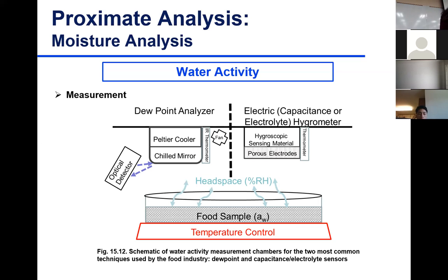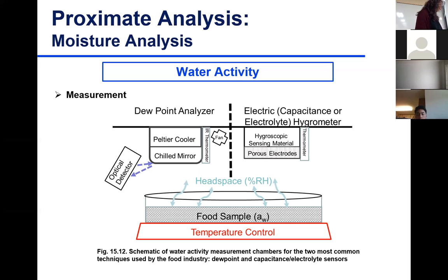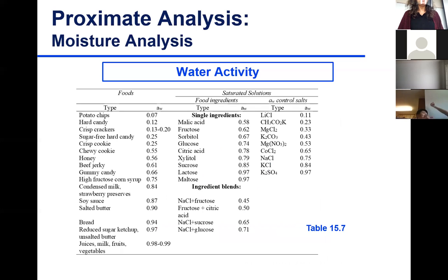In the electric hygrometer, you have a hygroscopic substance that either loses or gains moisture based on the relative humidity of the environment. Any change in conductivity detected at the electrodes — due to changes in absorption by the hygroscopic material — is measured. Changes in conductivity or capacitance give you the water activity reading.